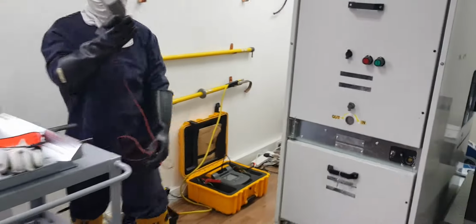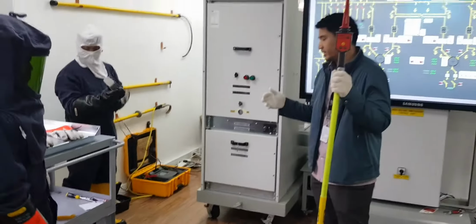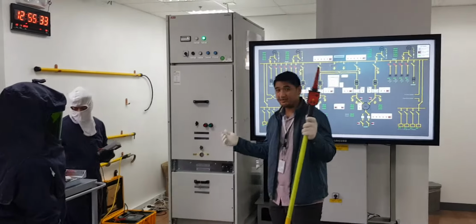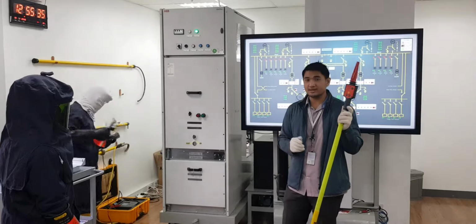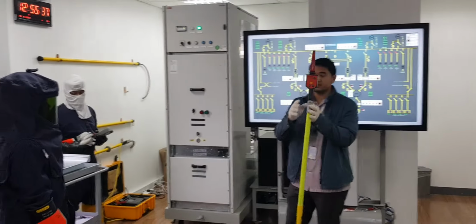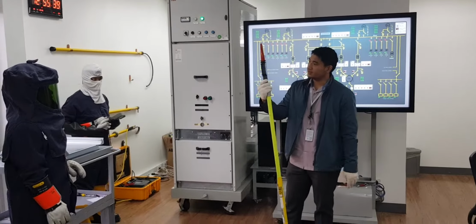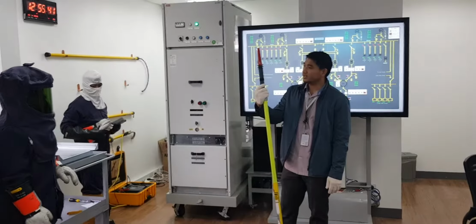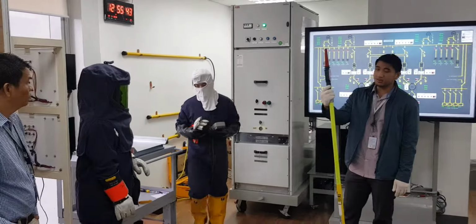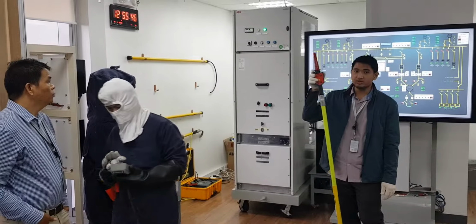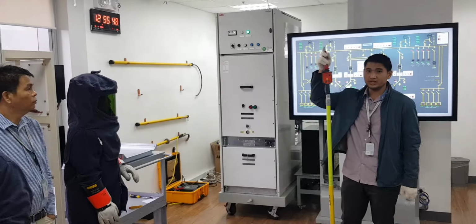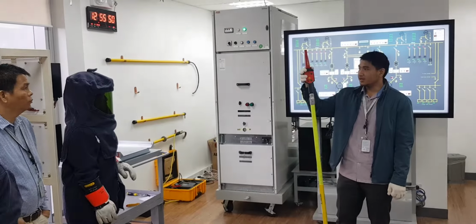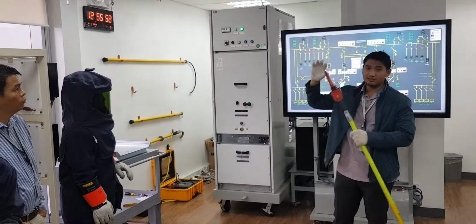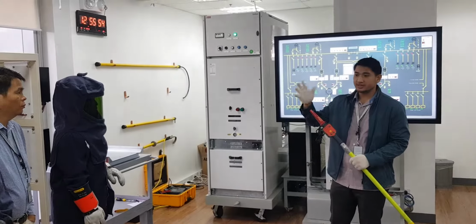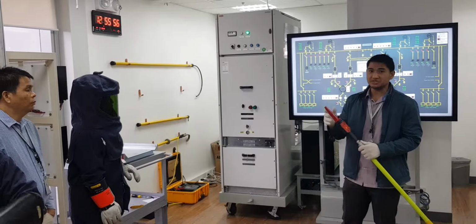Okay, so we're about to do the activity of racking out the circuit breaker, and then we have the line side, so we have voltage on the line side. Also to emphasize, this model, made by Amprobe, model TIC 300 Pro AC voltage detector, is designed to detect such voltage, which is around 800 volts, at a distance of even 27 inches, around 2 feet and 3 inches.